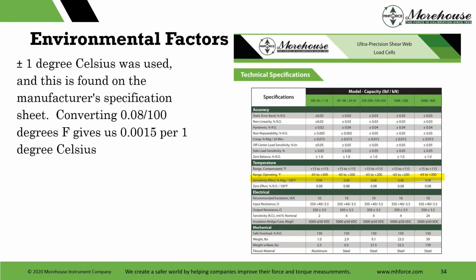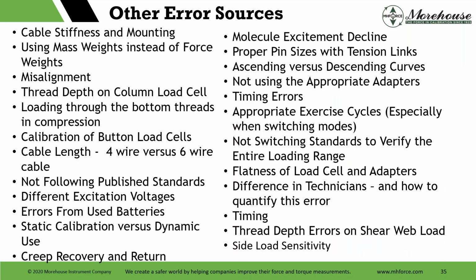The other things you could add in here: zero effect unrated, you could look at this. You could also look at side load sensitivity. We look at this a lot. You can look at creep. Some of this stuff that people do throw in, a lot of times, depending on how you're taking your return to zero and whatnot, is often counted as part of your R&R and your repeatability. You're going to detect some of this stuff inherent in the system, especially if you run control charts, which I cannot recommend enough. Over time you're going to balance some of these out, and that's why I'm not calling on them specifically in the examples.